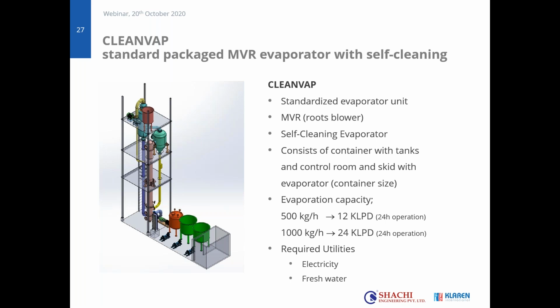So this was the third item that I wanted to illustrate in how to design, select and look upon MVR units. Currently, together with Shachi, we have developed a standard package, an MVR unit with self-cleaning. For the smaller units, it's based on the roots blower. It's containerized, so it will consist of a skid with a containerized unit that contains the tanks and the circulation pumps. We have standardized capacities. Of course, they will fluctuate a bit based on the concentration ratios that you want to achieve. But we try to have a standardized unit so that we can go to a more low-cost unit. And the only required utilities would be electricity and fresh water.